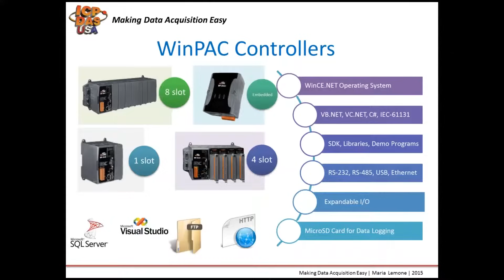We have rack-based and embedded versions. Our WinPAC comes in embedded 1-slot, 4-slot, and 8-slot rack versions. The embedded type can be used with an expansion I/O board inside and with remote I/O. The rack-based types can use cartridge-based I/O and remote I/O. They all come with micro SD cards for data logging, a software development kit, libraries, and demo programs. They're fanless, have ventilated housing, and are designed for use in extreme temperatures.